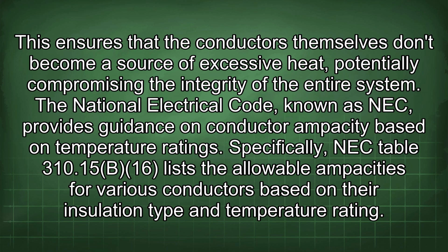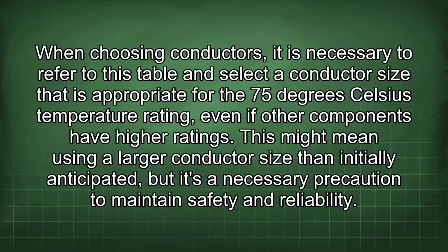The National Electrical Code, known as NEC, provides guidance on conductor ampacity based on temperature ratings. Specifically, NEC Table 310.15(B)(16) lists the allowable ampacities for various conductors based on their insulation type and temperature rating. When choosing conductors, it is necessary to refer to this table and select a conductor size that is appropriate for the 75 degrees Celsius temperature rating, even if other components have higher ratings. This might mean using a larger conductor size than initially anticipated, but is a necessary precaution to maintain safety and reliability.